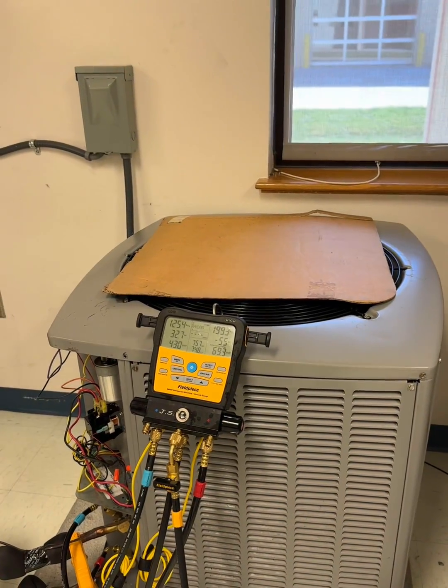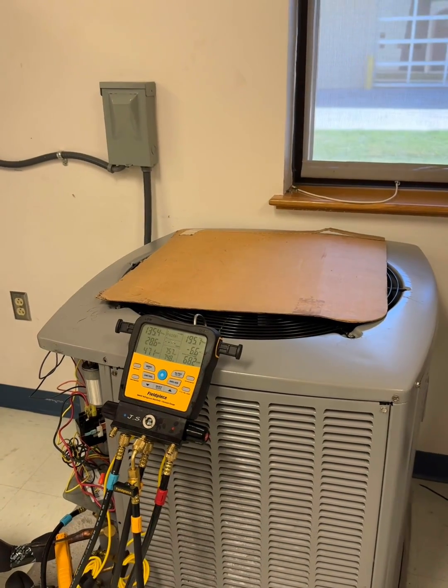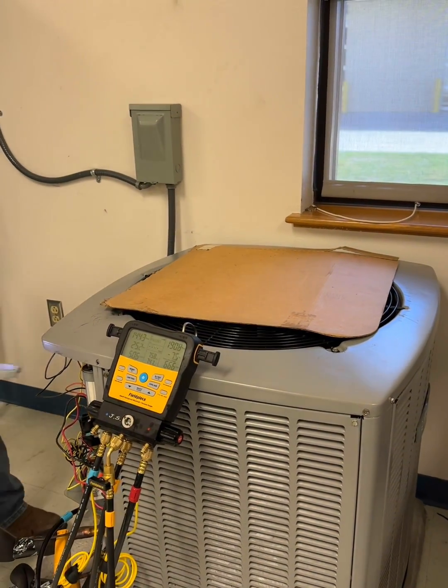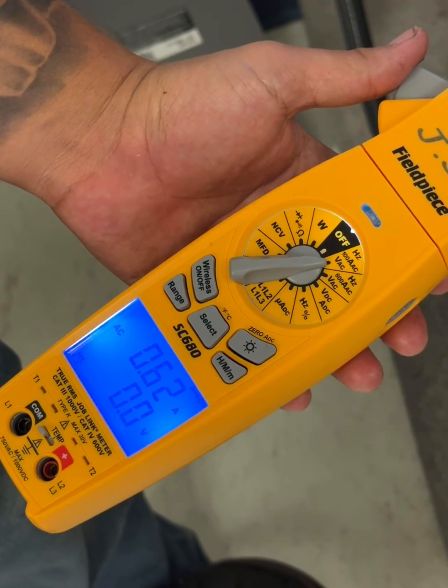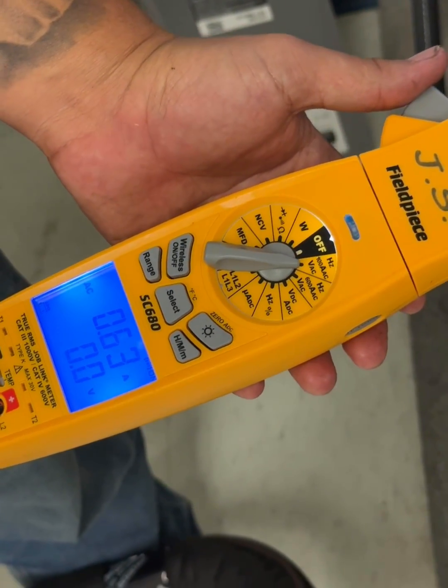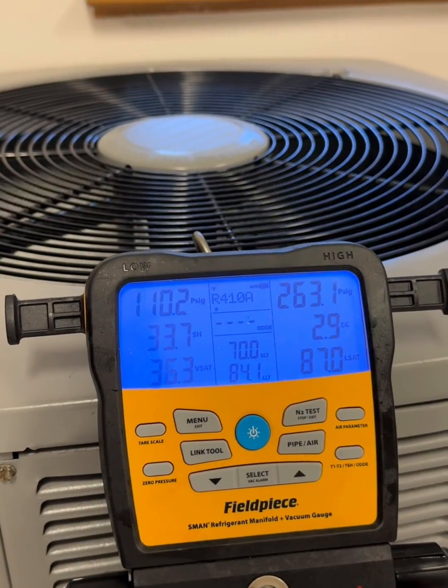A condenser restriction causes high head pressure, which leads to inefficient cooling, but could also lead to a burnout of the compressor, which works harder due to the restriction.